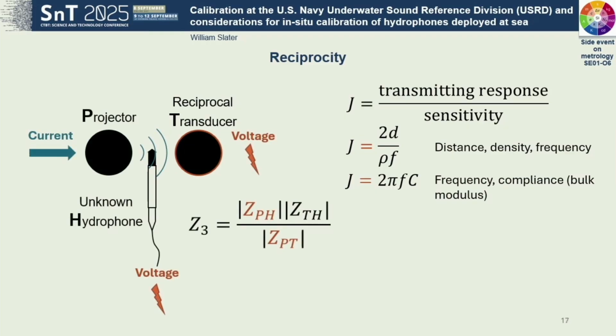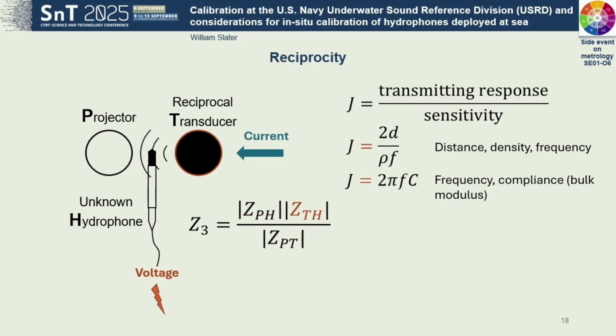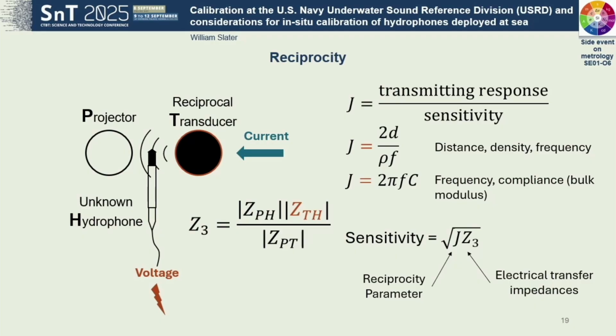To carry out this method, you measure 3 electrical transfer impedances contained in this Z3 parameter. Two driving with the projector and recording with the unknown hydrophone and reciprocal transducer, and the third with the reciprocal transducer driving and the unknown hydrophone recording. This ordering sets up the ratios required to form the reciprocity parameter and replace transduction properties of the reciprocal transducer with physical properties of the fluid medium and boundaries. We are left with the sensitivity of the unknown hydrophone without reference to any other transducer response, which is a primary calibration.